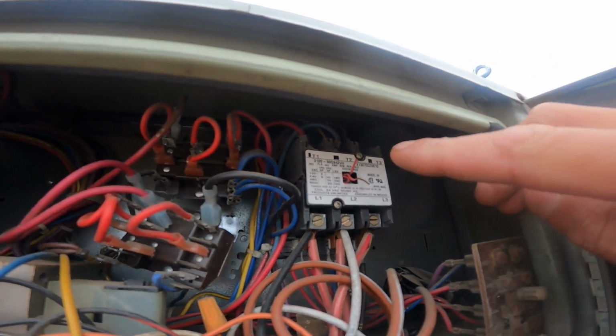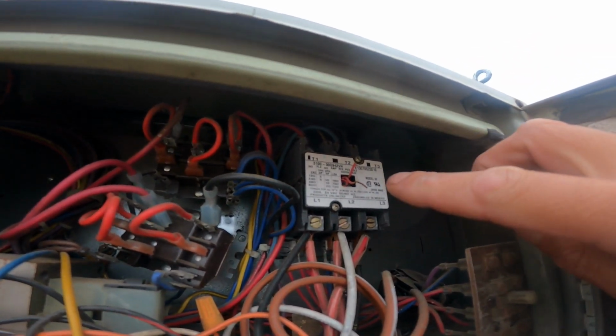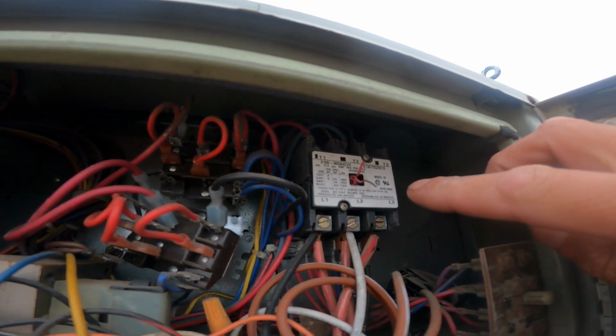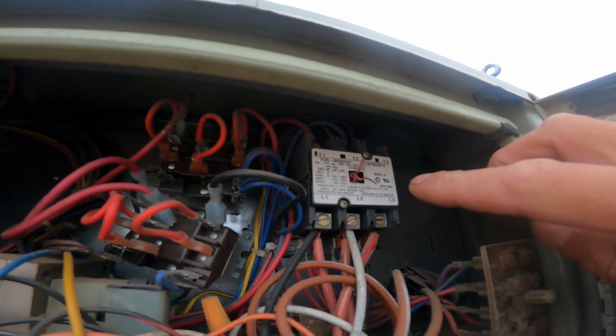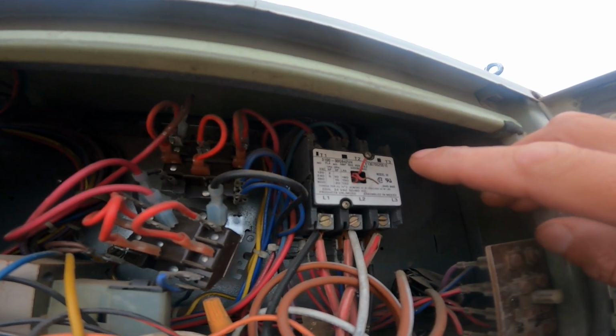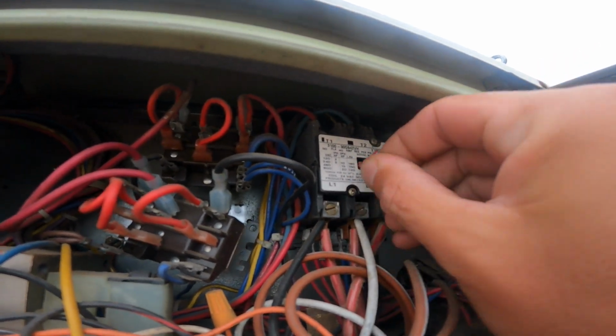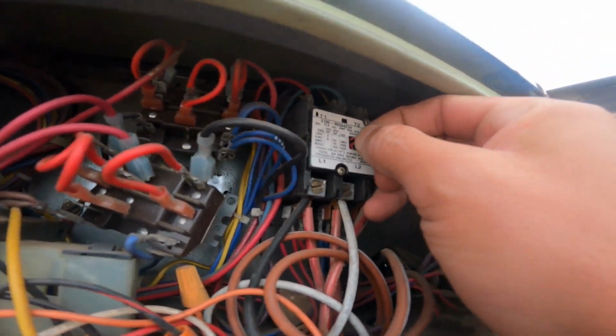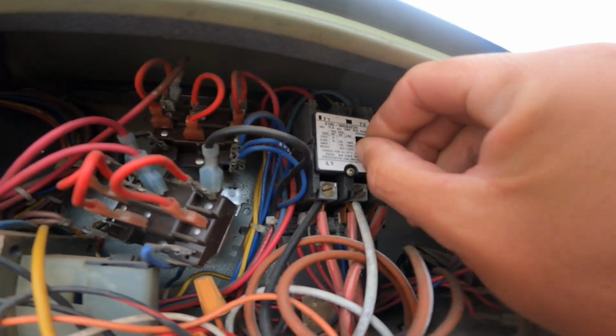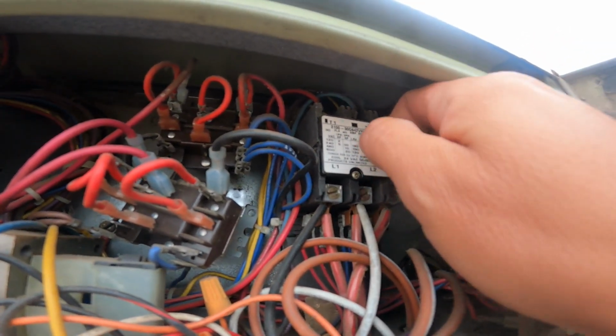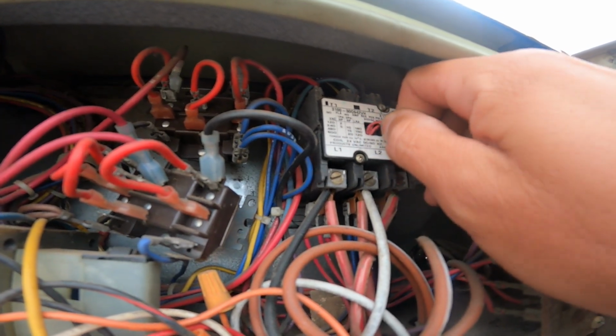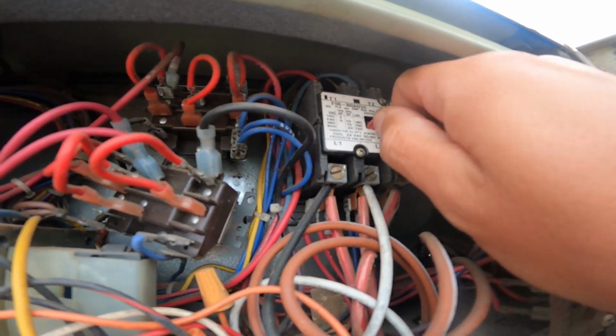Guys, that is a hack of all hacks. You shove a piece of thermostat wire to hold the contactor in instead of figuring out what's wrong with the unit and fixing it. That is so wrong on every level. That's like holding a breaker closed that keeps tripping. You're gonna create a fire, people. You're gonna burn the house down.